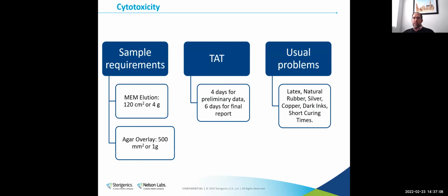If you don't know what cytotoxicity is, I'm going to talk a little bit about it, but cytotox is the most sensitive biocompatibility test we have. So at Nelson Labs, we did a quick, or it wasn't quick, it was over 10 years, we did just an overview of our failures. So anytime a test failed at Nelson Labs over a space of 10 years, we recorded it. And 96% of the time, it was cytotoxicity. Okay, so that means only 4% of your failures are going to be anything else in biocompatibility. 96% of the time, at least per our data, it's going to be cytotox that fails.